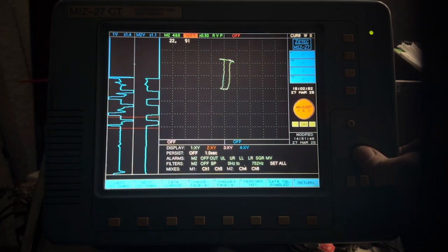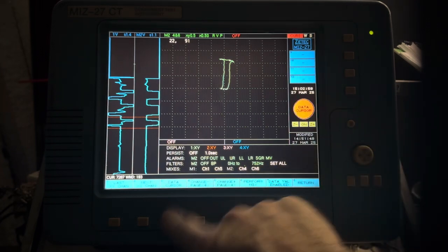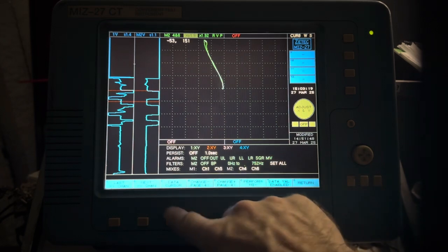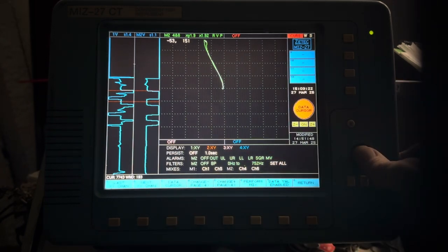So that would be, oh, it's probably about a 20% wear scar. And then when we go up to the next one, it's going to go off screen. That's 60%, 40%, I mean. Then the next one's going to be 60%. So I'll bring this one back down on the screen using my gain control here. So that's 60%. Now this is an absolute mix, right? So that's 60%, 40%, and that's the 20%.